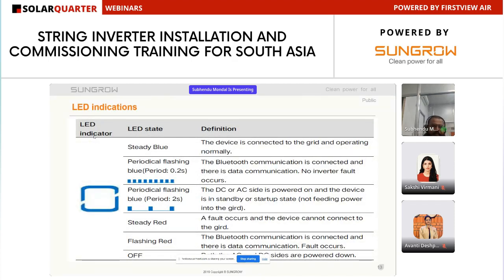Here is the LED indication. By seeing the LED indication we can easily identify the status of the inverter. If it is steady blue, that means the inverter is working normally, on grid and in fully operational mode. If it periodically flashes, that means communication is connected, for example a mobile is connected with the inverter through the iSolarCloud app. It is periodically flashing every 2 seconds. Then AC or DC powered on, standby or startup mode. It's not totally on grid. It is either standby mode or startup mode.